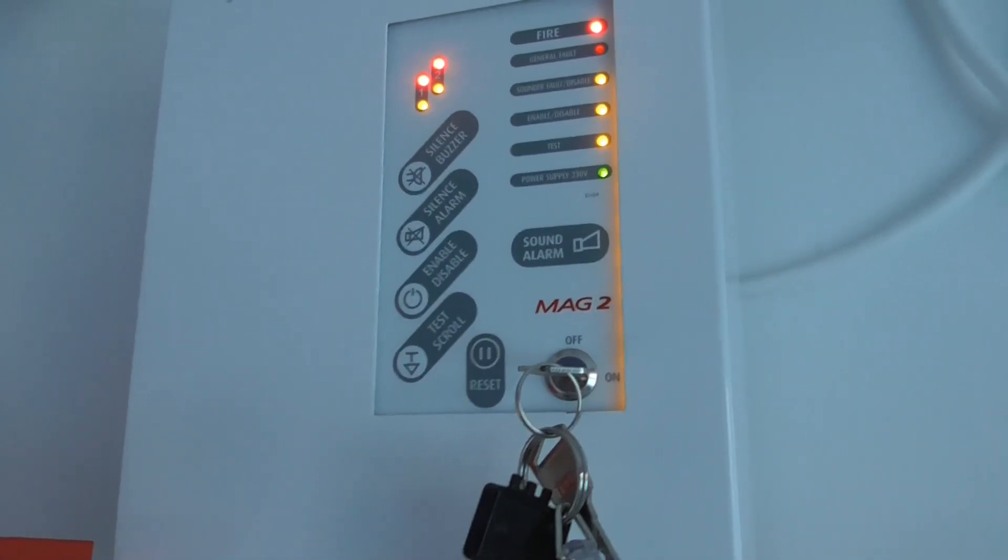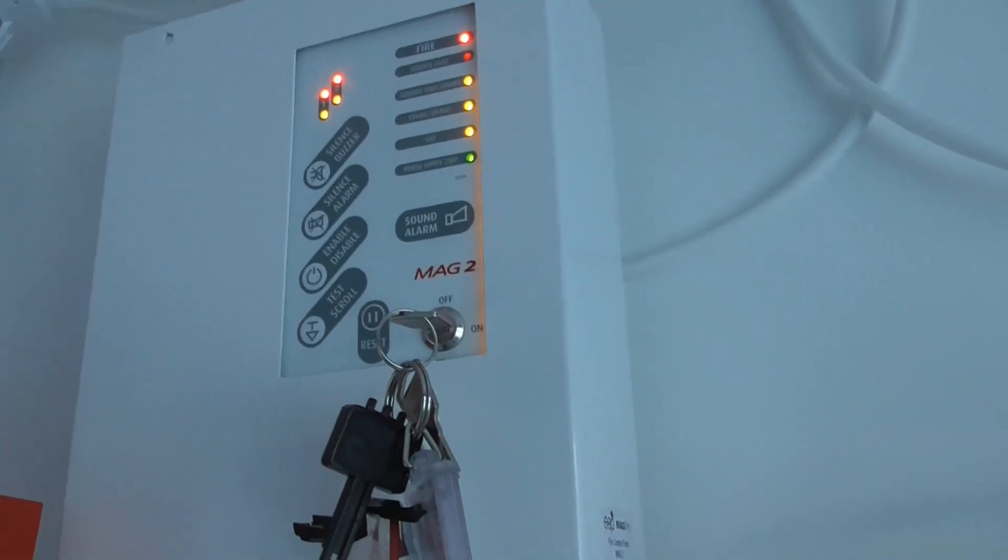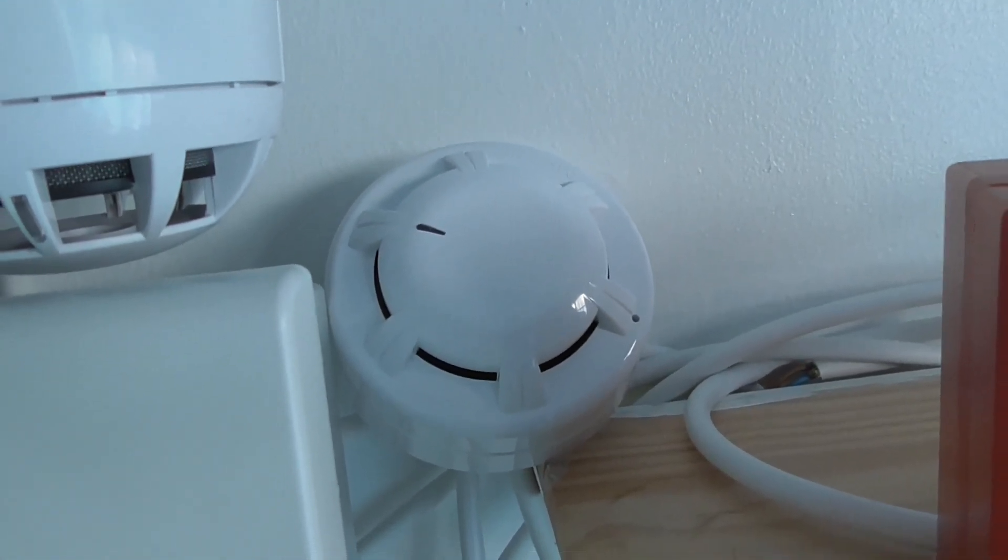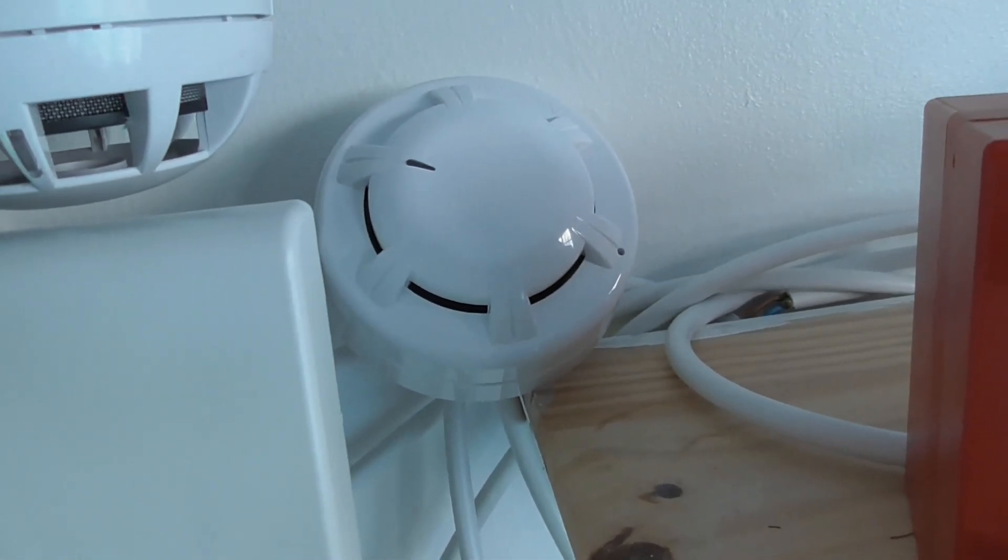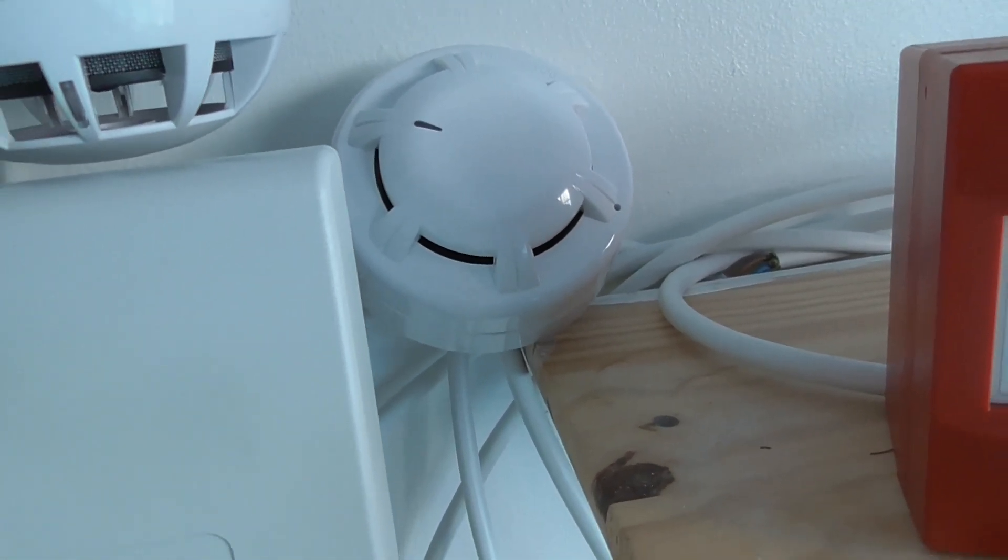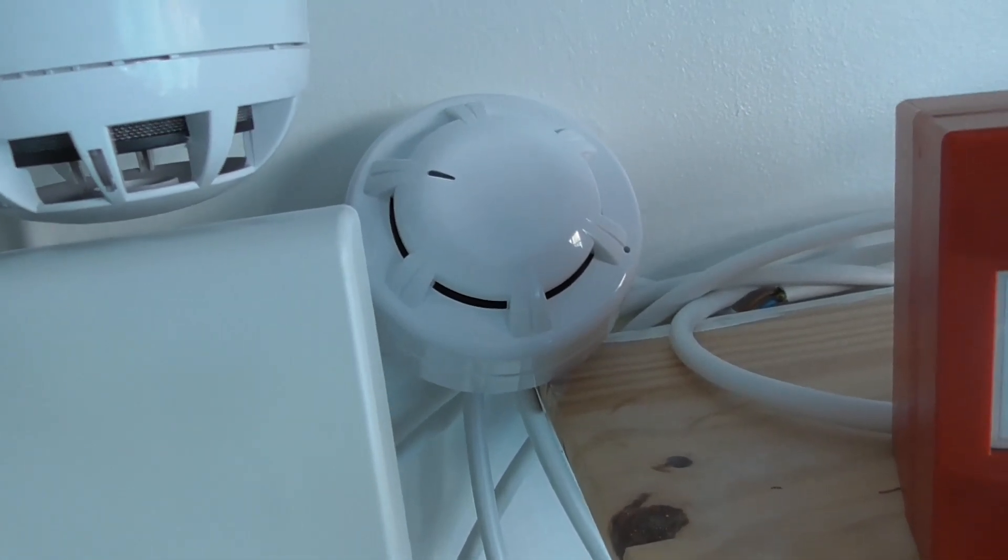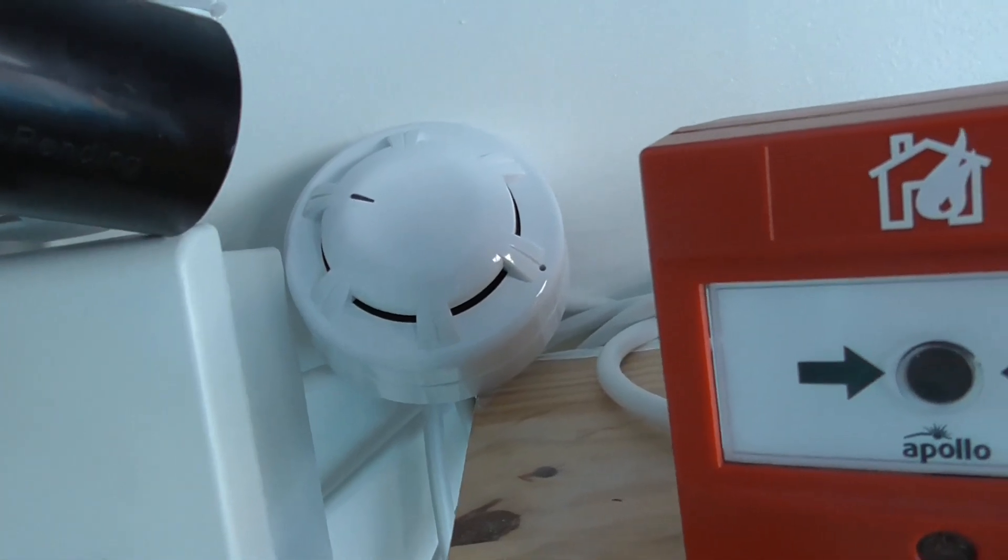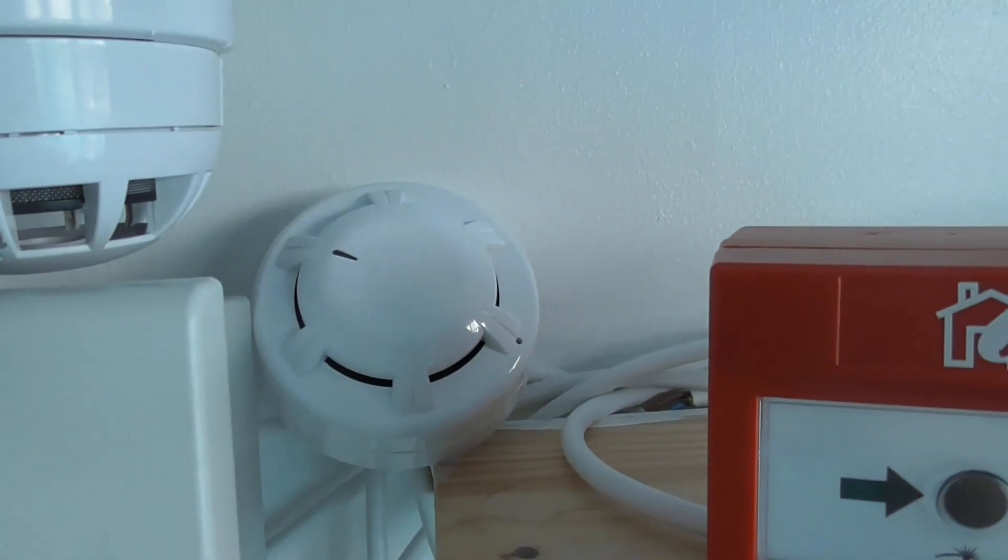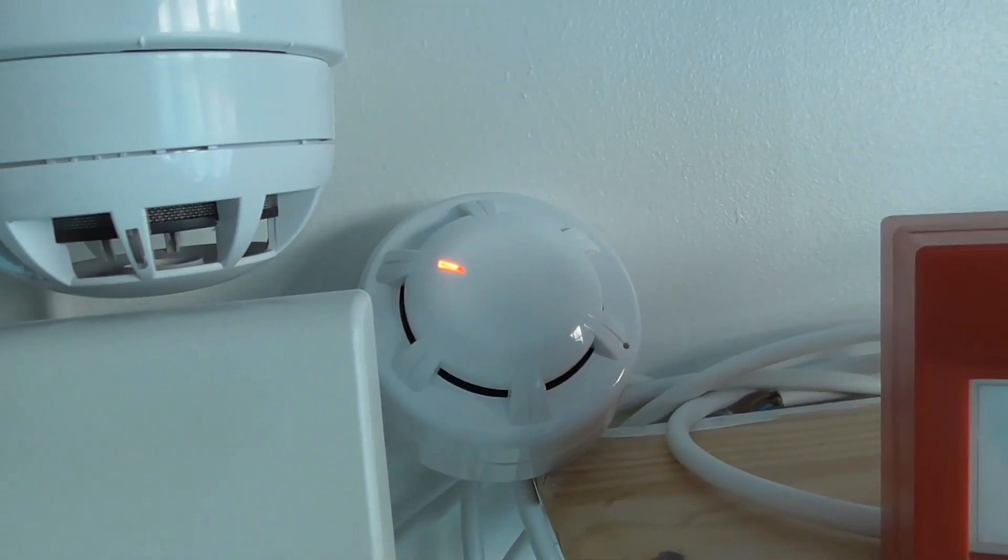Now let's test the Apollo Orbis detector, let's give the Orbis a quick test. Also, the Apollo Orbis does poll really quickly when it resets, when the panel resets. It has like a five minute startup or something, so it takes a couple minutes to start up, and then it polls normally. Anyway, let's give this a test. Here we go. See if that goes off. There we go.